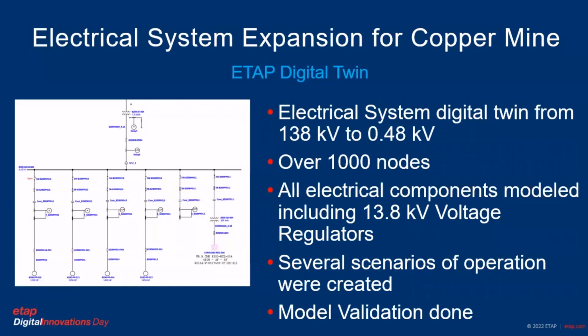So we started with the ETAP digital twin, which was elaborated by our company right from the ground. The transmission high voltage level is 138 kilovolts. The distribution level is about 13.8 kilovolts, and then the application voltage to the loads is 4160 volts and 480 volts. The size of the digital twin was around 1,000 electrical nodes.